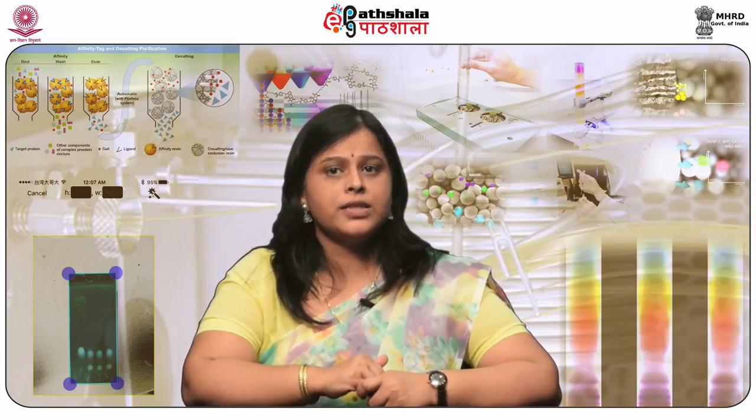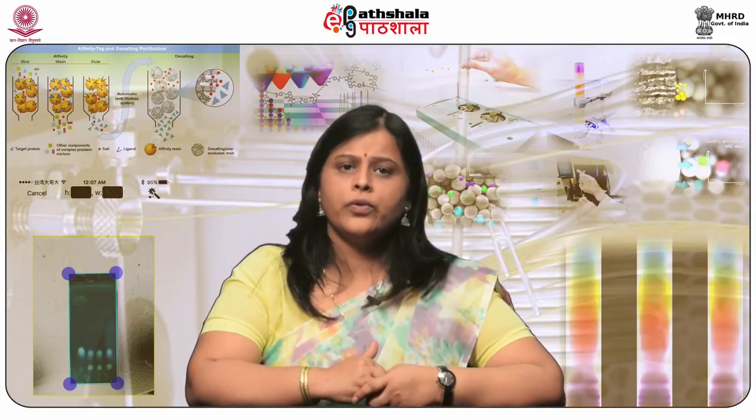In this module, we will understand the basic instrumentation of supercritical fluid chromatographs. We will summarize the historical developments in SFC instrumentation. SFC technology could be applied practically in the 1980s only after a commercial subsystem was introduced by Hewlett Packard. The popular SFC system of early times consisted of capillary columns, an oven, pure carbon dioxide as mobile phase, a pump for pressure or density programming, and fixed restrictors to maintain pressure with flame ionization detectors. However, early equipment suffered from long retention times and low efficiency.